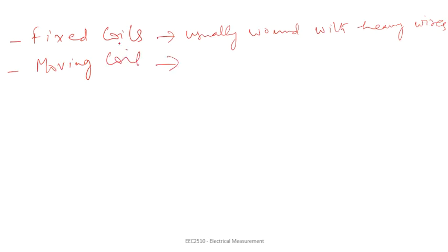Next we have a moving coil, which is the same as in previous instruments also, which we have discussed in PMMC type instrument. A single element instrument has one moving coil, and the moving coil is wound either as a self-sustaining coil or else on a non-metallic former, or frame we can also call it. This is the purpose of the moving coil, that whatever the magnetic field is being produced by the fixed coil, the moving coil will be acted upon by that.